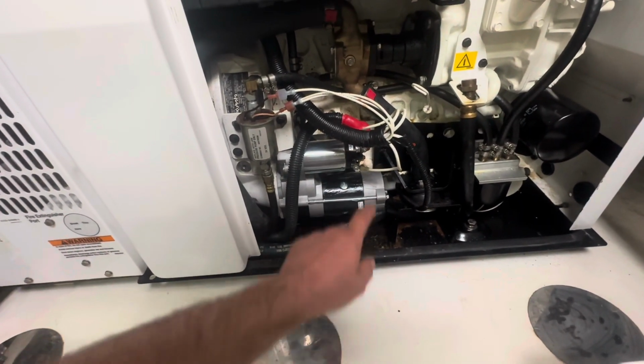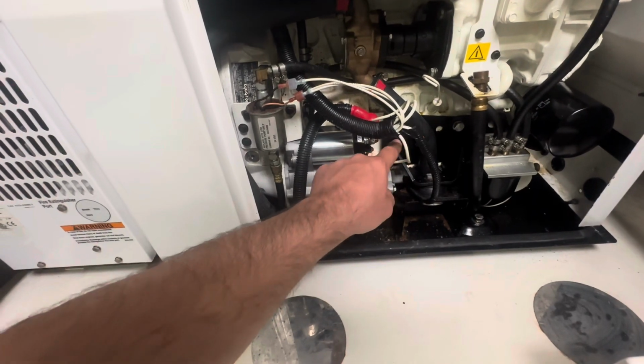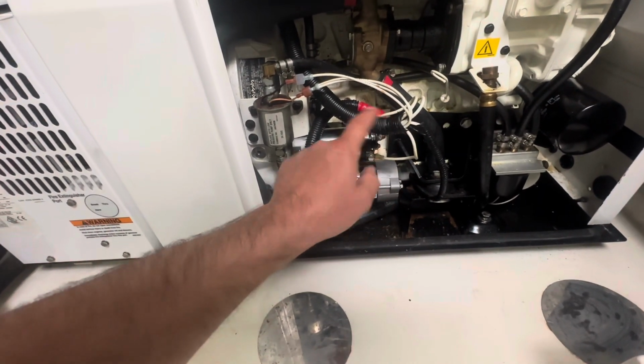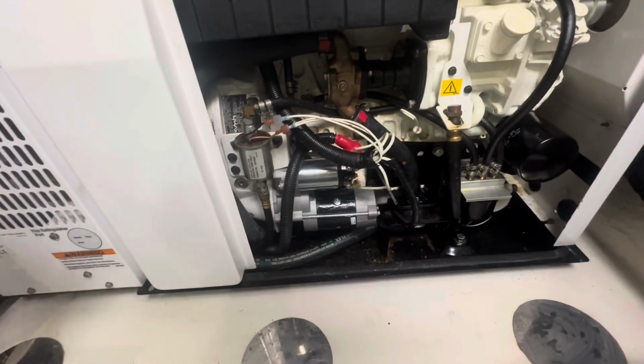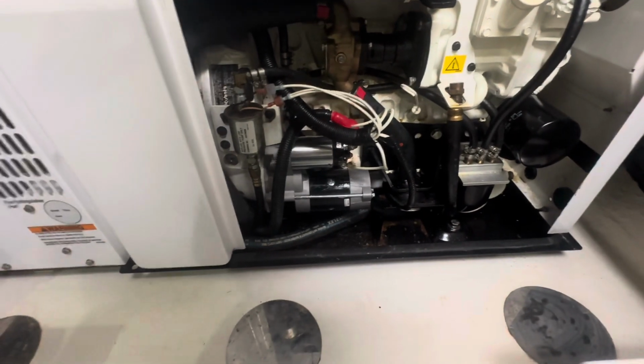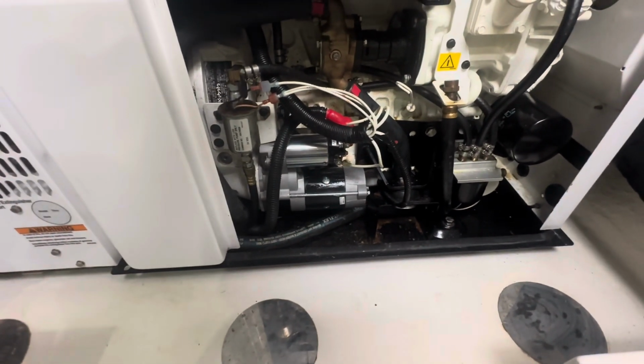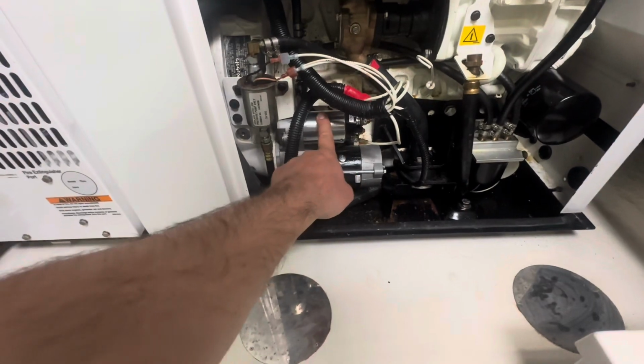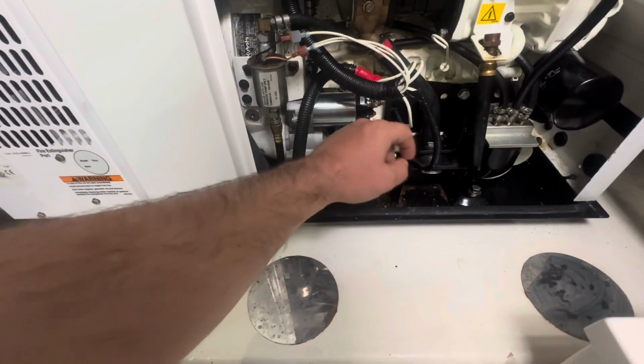So it would make sense that if we had a faulty connection or bad corrosion, it might throw a code to the generator ECU saying we've got too much voltage, when we really don't. So this morning I threw the starter on, cleaned the connections, put it all back together, and ran the generator three separate times.